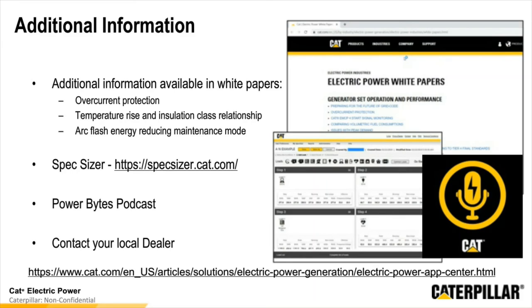There's even one on our arc flash energy reduction mode, which is basically the ability to provide a setting to the generator set that will reduce down the protective settings to allow you to do more maintenance on the product and allow our maintenance teams to be able to work safely in a safe environment. This aligns with the NFPA 70E requirements that you'll see in many areas.